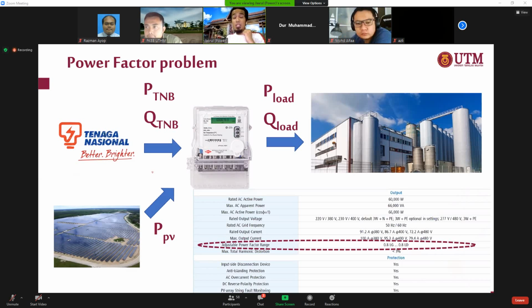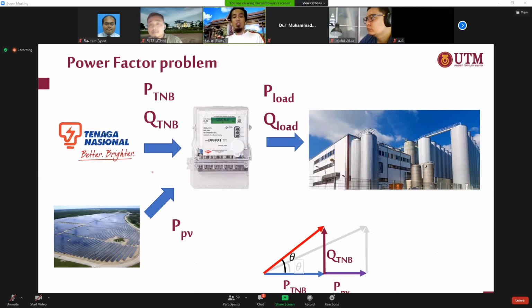But we still need to be very careful. Sometimes even though the inverter is able to provide Q, if the Q is not enough, the factory might still get a power factor penalty. There are a few cases that I have experienced. So we need to install an external capacitor bank to support the PV, so that the factory or industrial user will not be penalized by TNB due to low power factor. So I think that's all about my presentation.